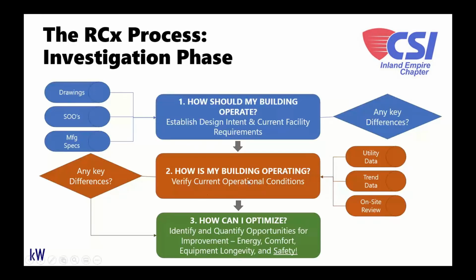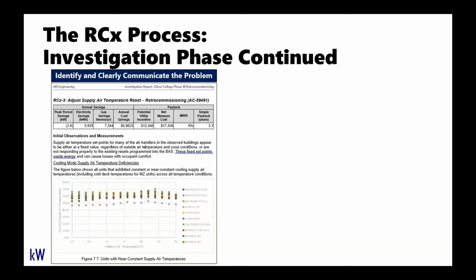So if we've identified that the current building is operating poorly compared to the design intent, then we can identify opportunities to optimize and restore the building to how it's intended to be run. And often that will lead to energy savings, improved occupant comfort, better equipment longevity, and, more importantly lately, occupant safety through maintaining proper ventilation in particular, and temperature control of the space. So this whole process, we apply through our engineering investigations, and the end result at the investigation phase is typically a report of our findings.